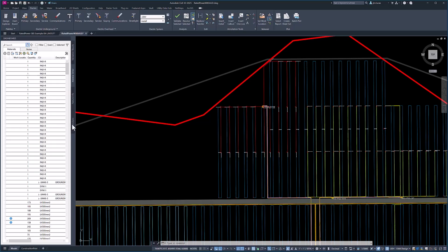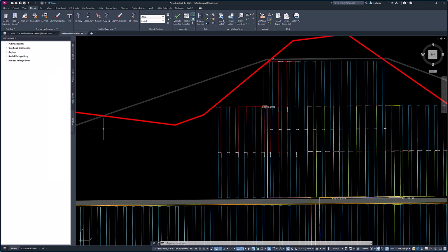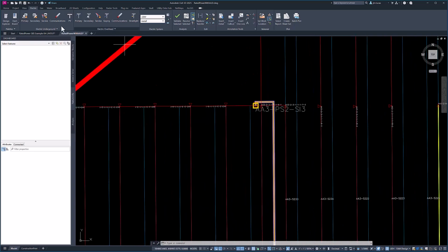Every time we make a change in AUD, it revalidates against your standards automatically. That includes engineering analysis and construction standards, like minimum trench depth or maximum conductors per trench, and drawing standards like line colors and symbology. If something falls out of spec, you know immediately before anyone gets to the field.